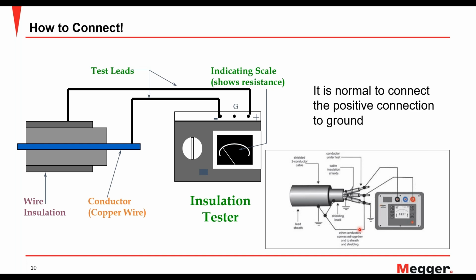Now, the important part: how to connect. A lot of it is simple, yet there's a lot of chance that it might be messed up, a chance of error there. Firstly, you have your test leads, a positive and a negative. Usually negative is the one going to the conductor, and positive is the one you're hooking up to the insulation or ground, whatever you're testing at. It is normal to connect the positive connection to ground, so that's what you are doing in this case. And positive is the one that is measuring leakage current. In analog style equipment, that's what it used to be, but in the digital ones, it doesn't matter much if you do it the other way around.